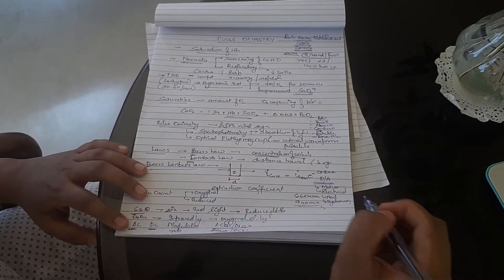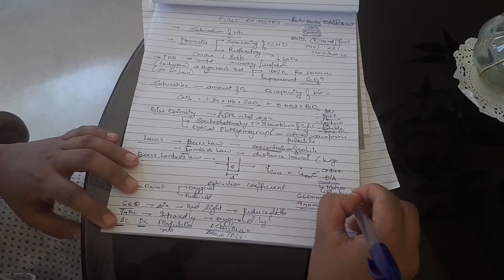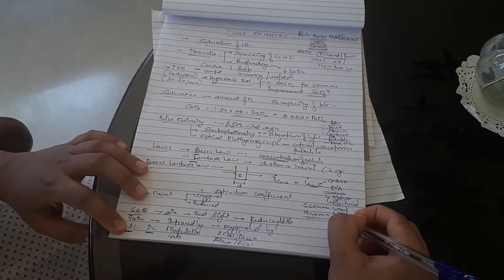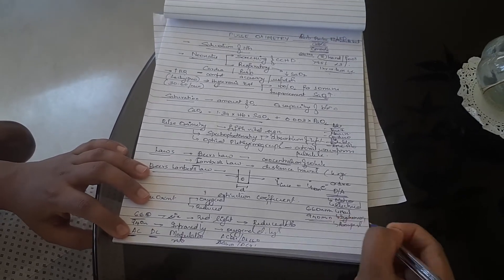One more problem: dyshemoglobinemia I told you, nail color I told you, electrical I told you. If the patient moves his fingers, it's going to be a problem. If the patient has poor perfusion, it's going to be a problem.